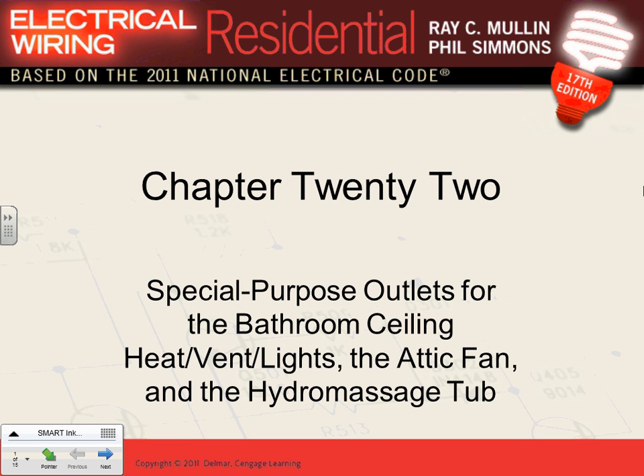to chapter 22, guys. Chapter 22 talks about special outlets for bathroom ceilings, heat, vent, attic, and hydromassage tubs. Let me summarize this with a few things before we even go there. A couple of things in the bathroom. Jamie, what do I need by code in the bathroom? I need one GFCI receptacle fed from what? A 20 amp dedicated circuit. So done. Here's a bathroom. So that's my bathroom.